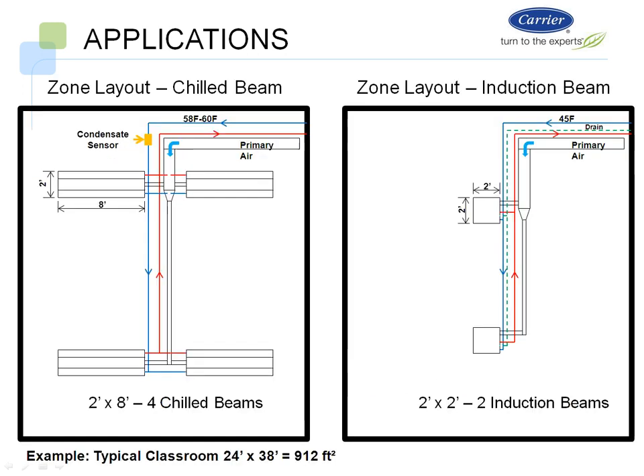So then when you look at that application in your zone layout, to the left here you see the traditional type chilled beam, where you would need 4 of those 2x8s, and you would only need 2 2x2s if you were using 45 degree water for the same type of classroom. Now the other thing I'll bring your attention to, and I'm not sure anybody sees my arrow going across my screen here, but if you look at these 2x8 units, and you look to the left of the units on the left, and to the right of the units on the right, you've got to be very careful, because if this was installed like this, you would have stratification up the right side of your room and the left side of your room.